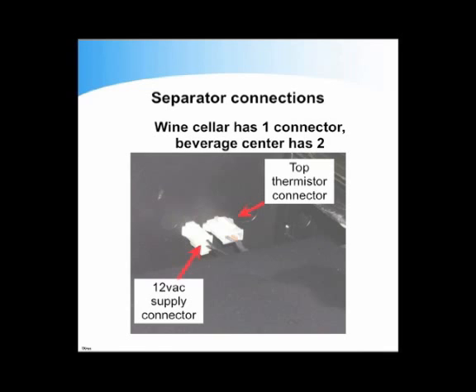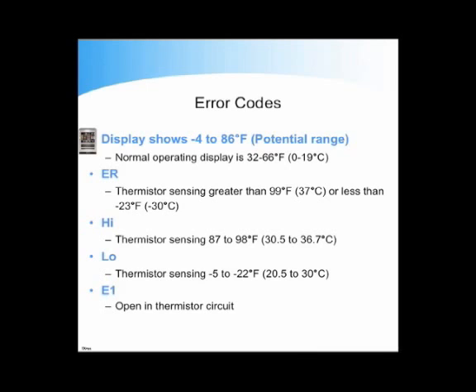The beverage center has the second connector to the top thermistor. Check the 12-volt AC. Error codes. Display shows -4 to 86 degrees Fahrenheit potential range. Normal operating display is 32 to 66 degrees Fahrenheit, 0 to 19C. ER: thermistor sensing greater than 99 degrees Fahrenheit, 37 degrees C, or less than -23 degrees Fahrenheit, -30 degrees C. High: thermistor sensing 87 to 98 degrees Fahrenheit, or 30.5 to 36.7 degrees C. Low: thermistor sensing -5 to -22 degrees Fahrenheit, -20.5 to -30 degrees C. E1: open in thermistor circuit.